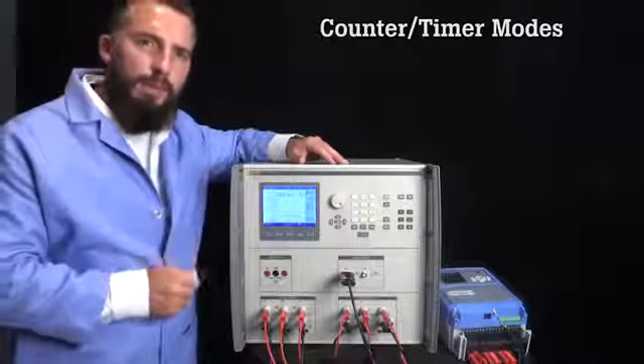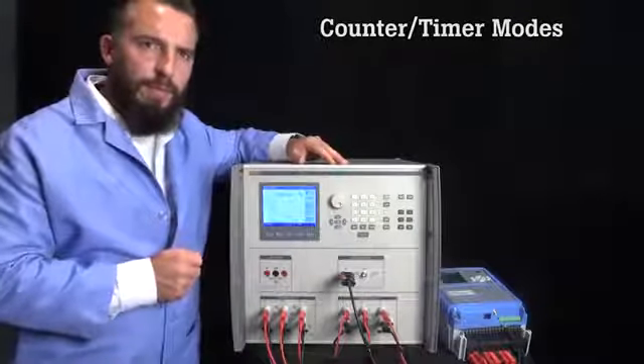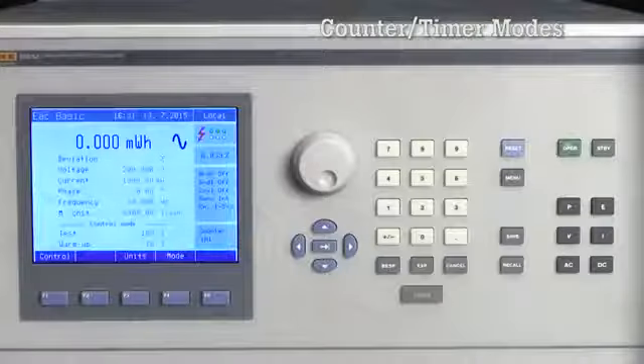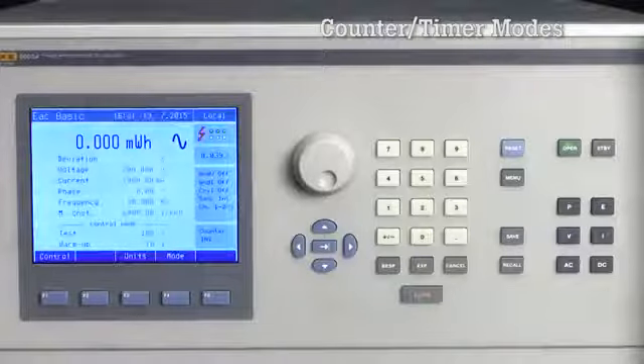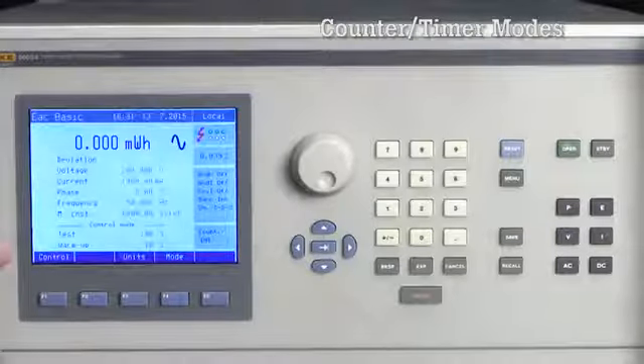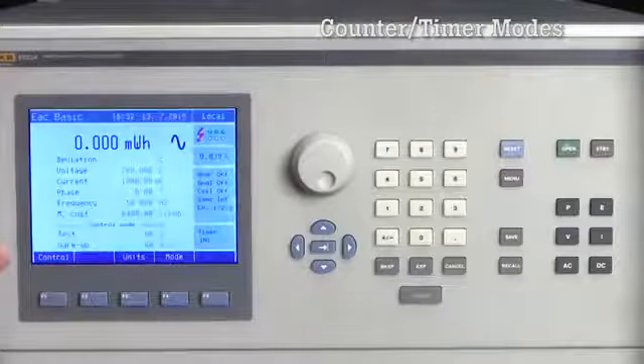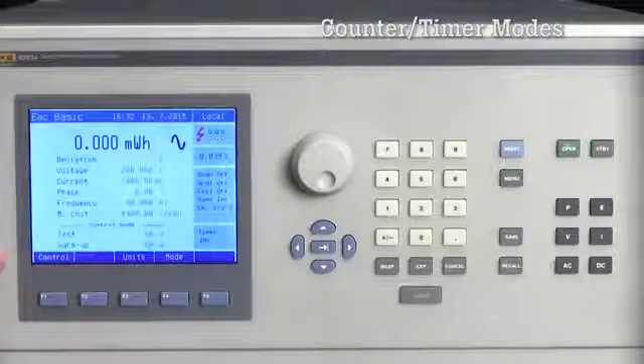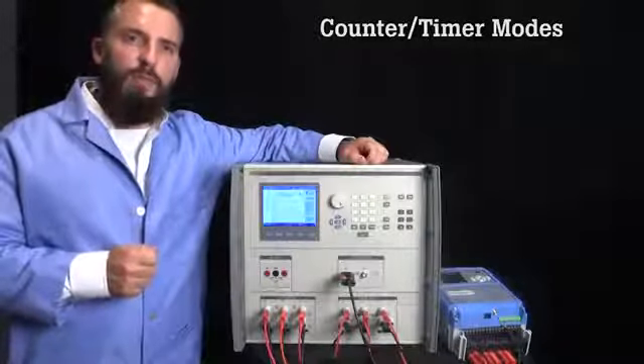To demonstrate, I've configured this test for 200 volts AC, 50 Hz, and 1 amp. If I use the counter mode, the 6003A lets you specify the warm-up pulses from the meter under test. If I were using the timer mode, I could set how many seconds I want the warm-up time in the test to run for, as I show here. For this demonstration, we will use the counter mode.